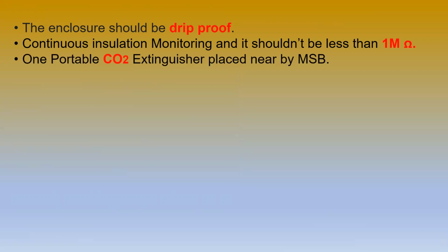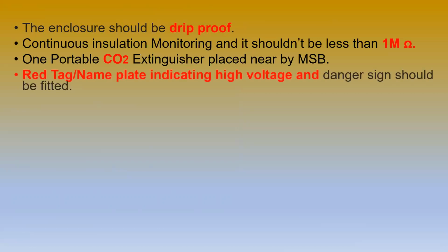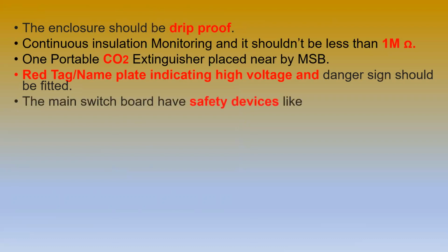And a portable CO2 extinguisher is placed near the MSB for any emergency. A red tag is used as a danger sign, and it is also fitted for a high voltage system. Normal high voltage cables will always have some charge with them that will not be dissipated. Even if we switch off the power supply, the cables will have some charge due to the high voltage. So it is better to put the red tag. That will be an extra safety.